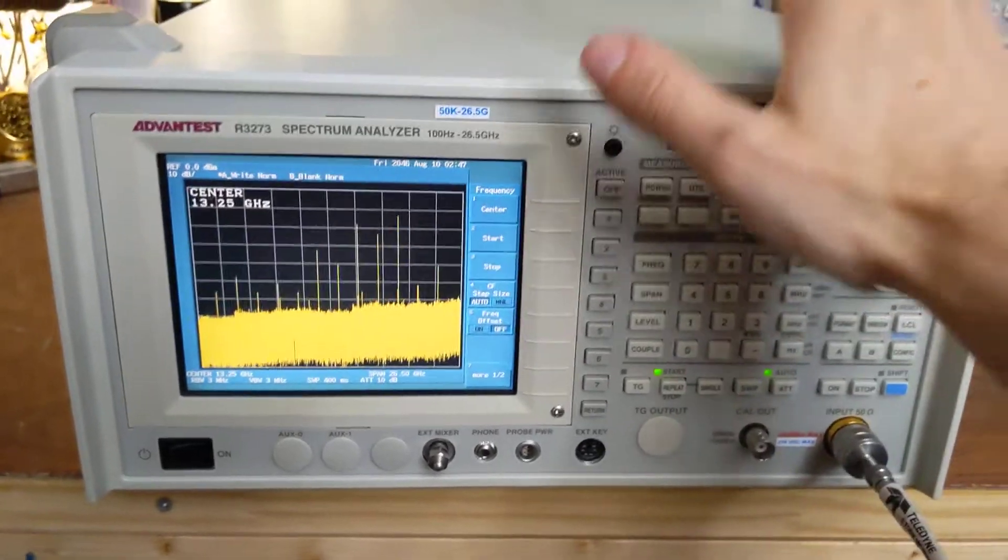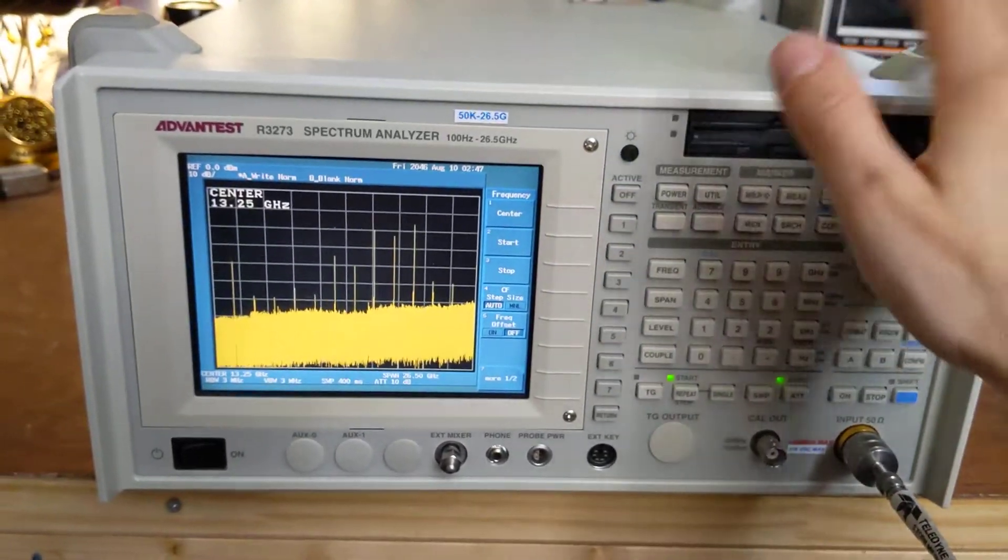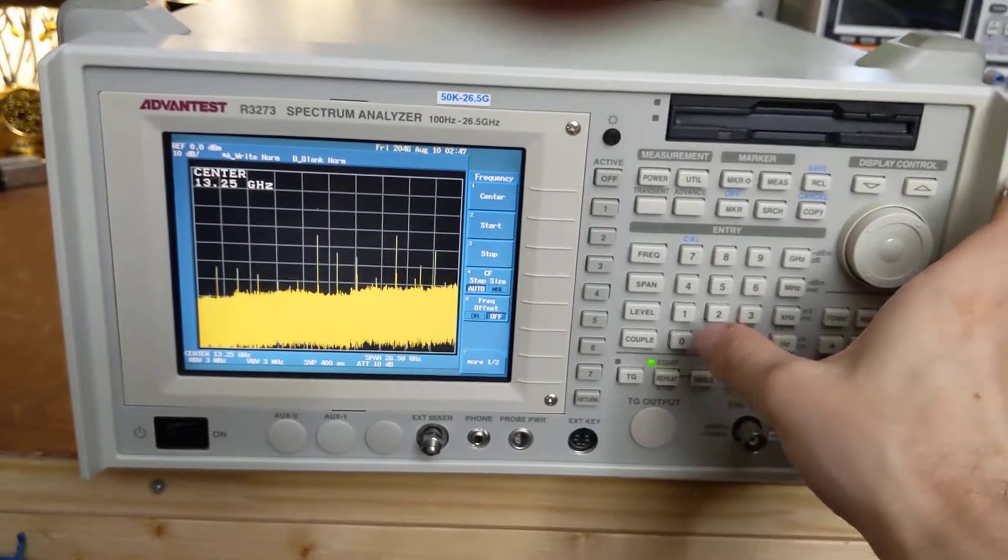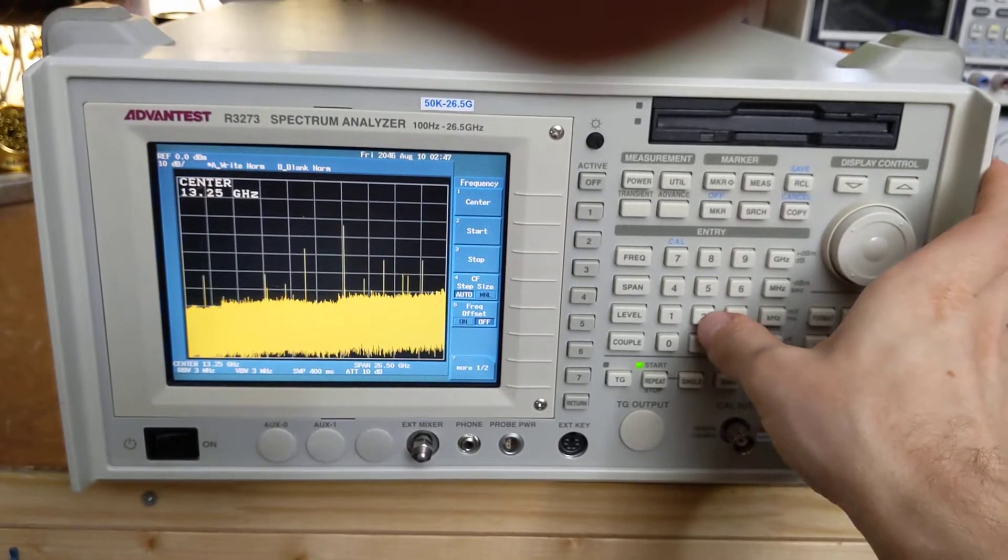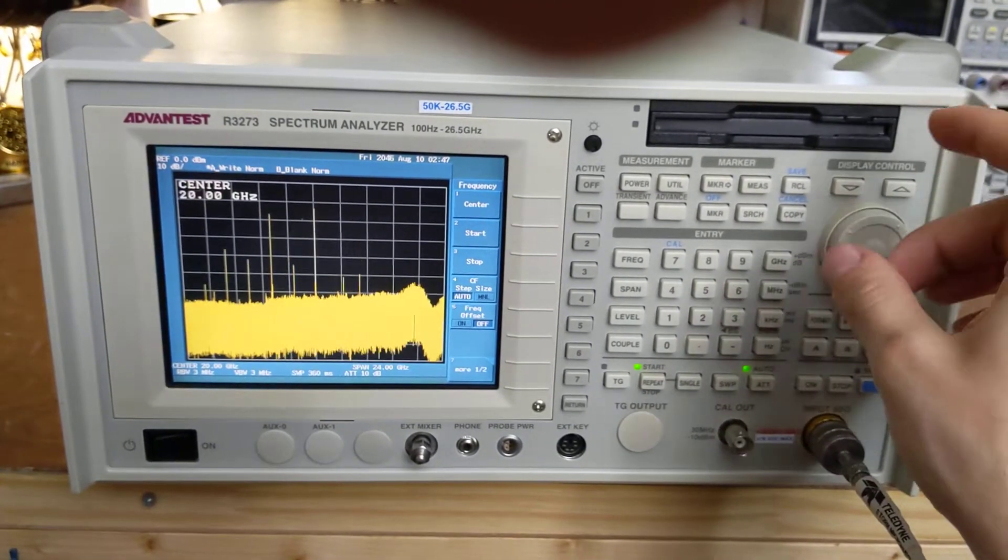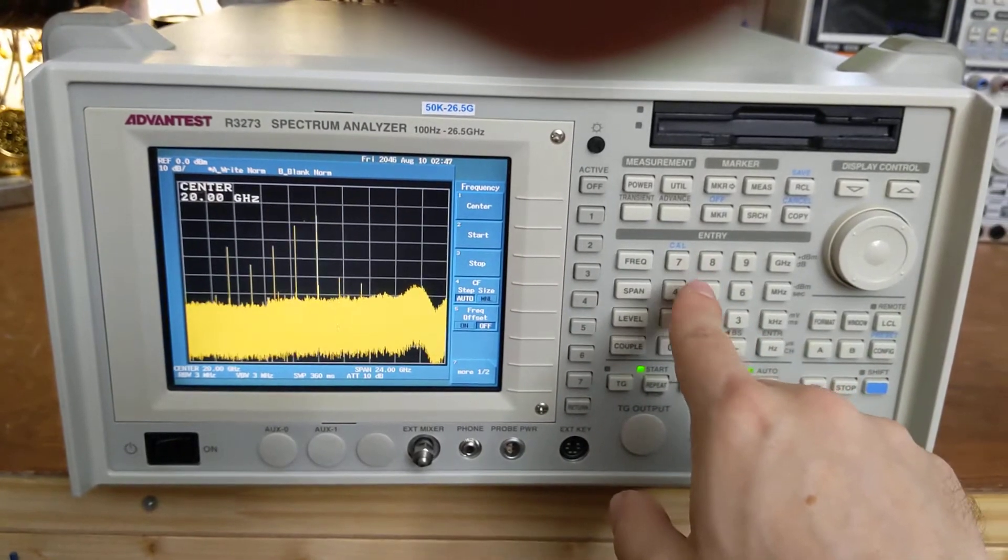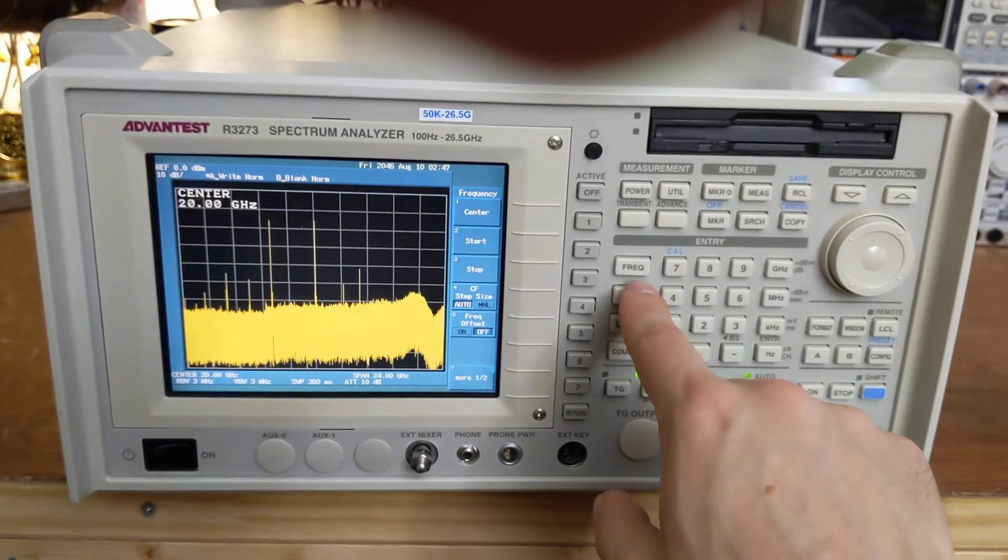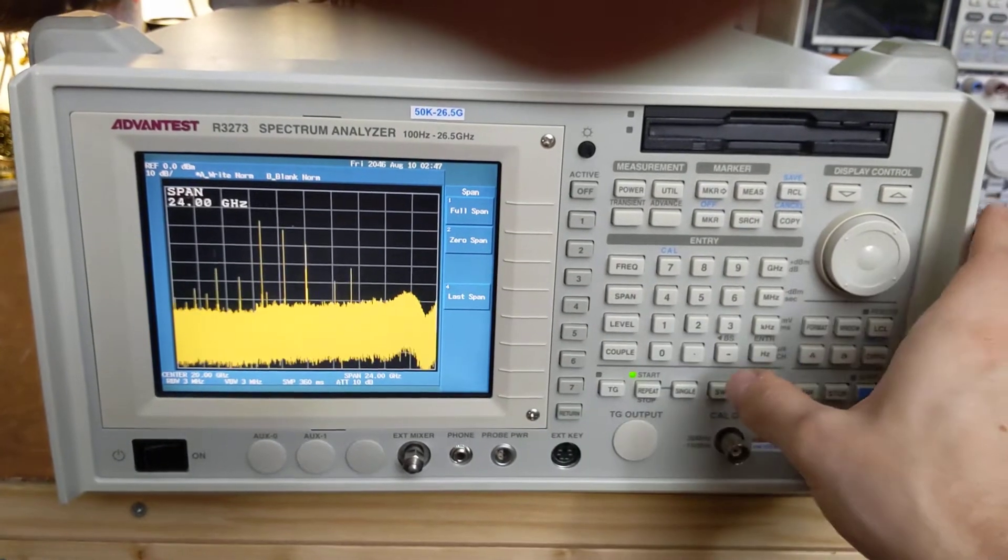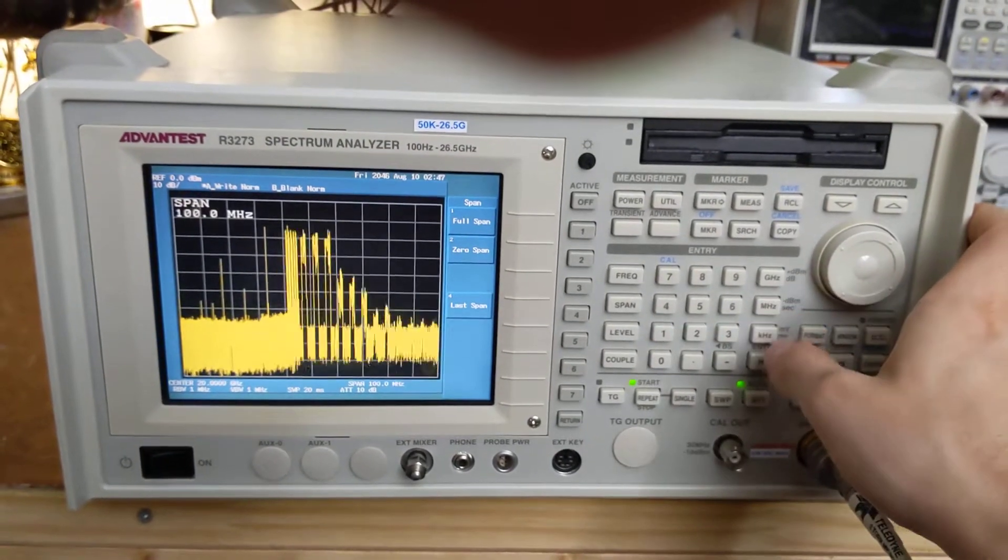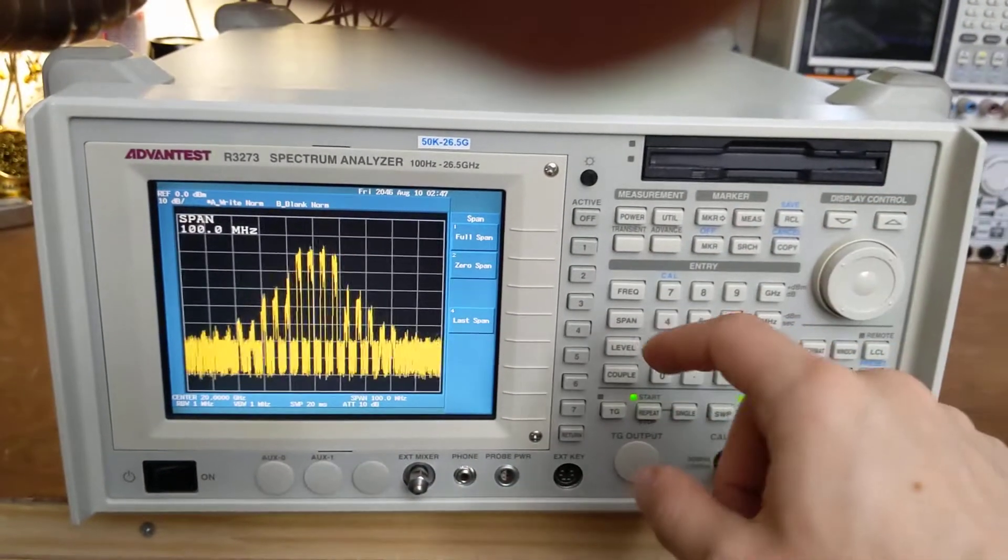So we're going to have to use the filtering that is inherent in the spectrum analyzer, the YIG-tuned filter, the little sphere of yttrium iron garnet that it's got there that allows it to bandpass out just the frequencies that it's interested in and reject all of the spurs. So frequency, 20 gigahertz span, let's say 100 megahertz here. So this is our signal again.